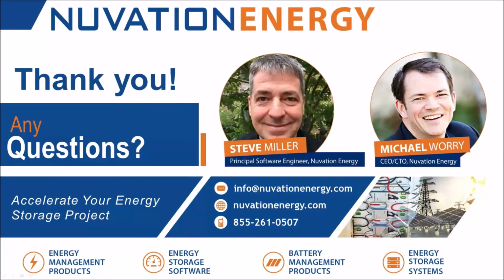Nuvation's done systems where, as Steve was saying, within an individual stack, you want to typically keep that to cells of a similar state of health and from the same manufacturer. But stack to stack, Nuvation's products allow you to mix and match different battery manufacturers, different states of health, different stack voltages, depending on what's needed for a system. Particularly if you use string inverters, you get good system flexibility. We've done energy storage systems that combine new cells with SecondLife cells, giving performance-cost trade-offs you can dial up and down system to system.